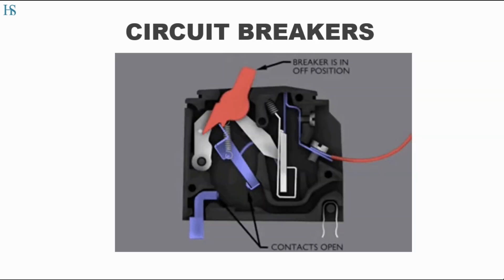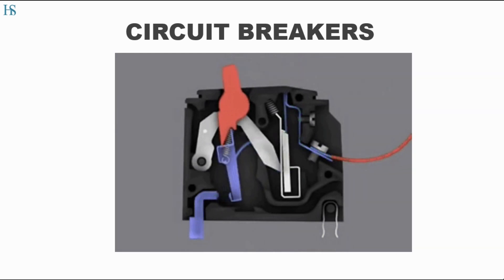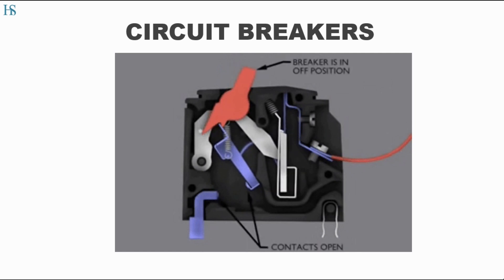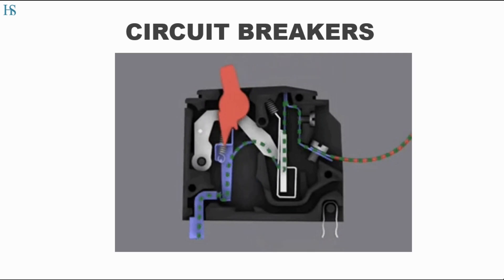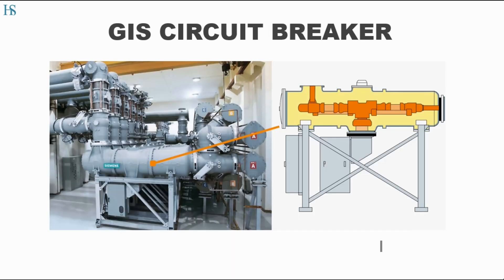Let me tell you in brief about circuit breakers. A circuit breaker is an automatically operated electrical switch. It is designed to protect the circuit from any damage. Its basic function is to interrupt the current flow during a fault condition, which may be caused by an excess current due to an overload or a short circuit. The current interruption is carried out by separating the two contacts. However, the current is still carried through an arc. In GIS, this arc is interrupted and cooled by using SF6 gas.